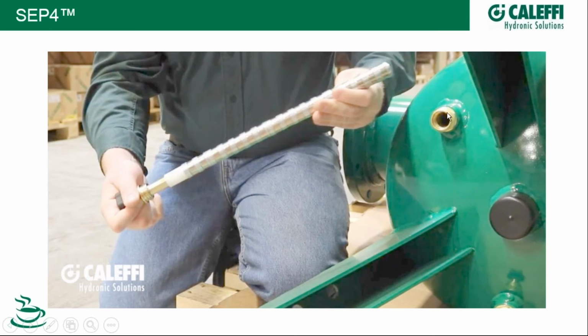It goes up into the barrel, and here you have a good photograph of the brass dry well. So the stack always stays dry. It's up in the dry well. Now, why do we use brass here? Well, magnetic flux lines that are needed to attract magnetic debris, the corrosion effects, pass quite freely through brass, but they don't through a lot of other metals, including ferrous. In fact, they're disrupted by ferrous metals. So that's why we use a thin-walled brass sleeve up through the belly of our commercial units.